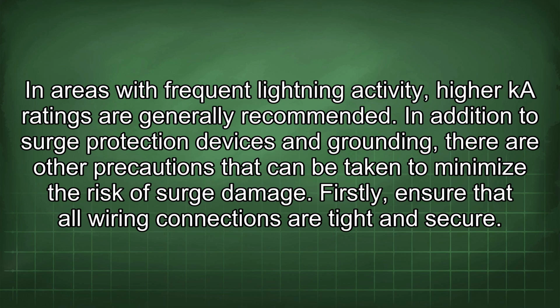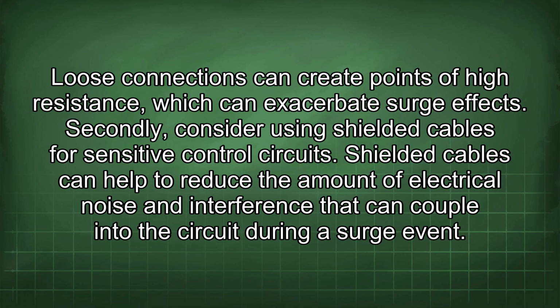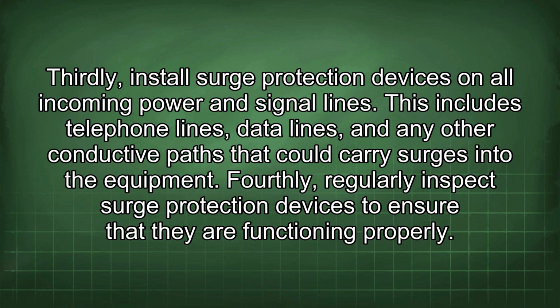In addition to surge protection devices and grounding, there are other precautions that can be taken to minimize the risk of surge damage. Firstly, ensure that all wiring connections are tight and secure. Loose connections can create points of high resistance, which can exacerbate surge effects. Secondly, consider using shielded cables for sensitive control circuits. Shielded cables can help to reduce the amount of electrical noise and interference that can couple into the circuit during a surge event. Thirdly, install surge protection devices on all incoming power and signal lines. This includes telephone lines, data lines, and any other conductive paths that could carry surges into the equipment.